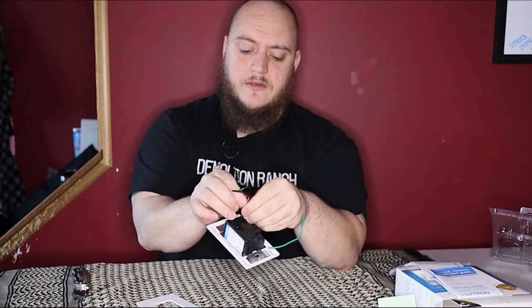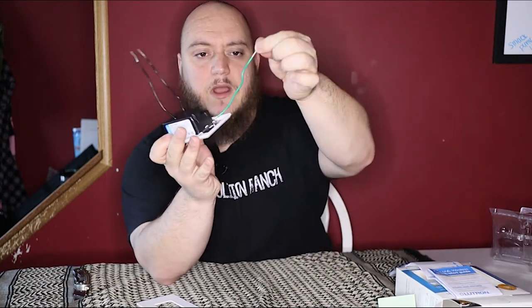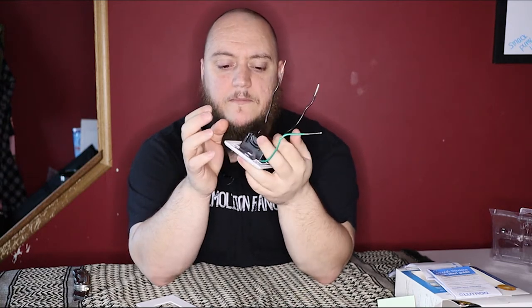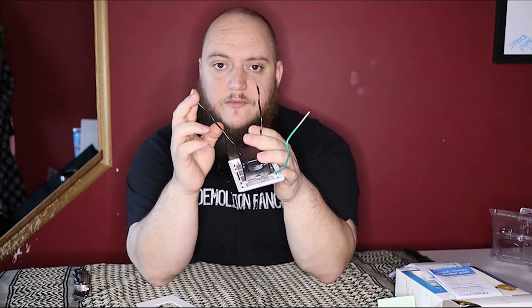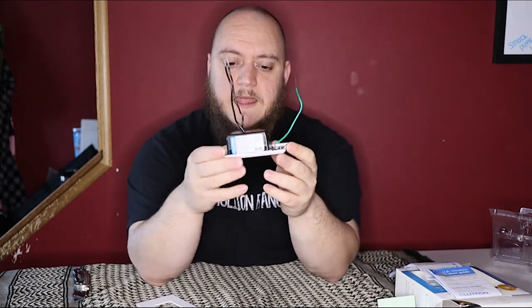Because you're going to have that third traveler wire, you open up these connectors — it's real simple. You have a ground wire which is green, and then two black wires. The nice part is it doesn't matter which of these you use; the board inside will correct which ones are which. One wire gets hooked up to the load and hot wire, the second to your traveler wire, which goes up the stairs to the other switch. Then upstairs you remove the switch completely and wire-nut all three wires together — your hot, load, and traveler — and push them back inside the box.